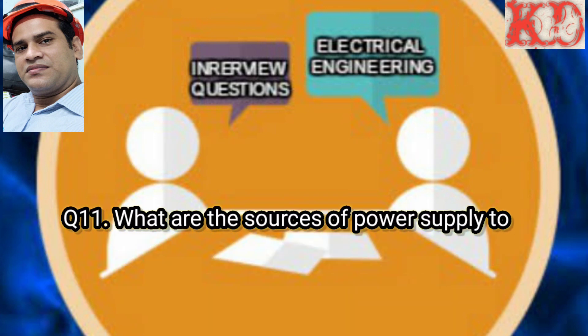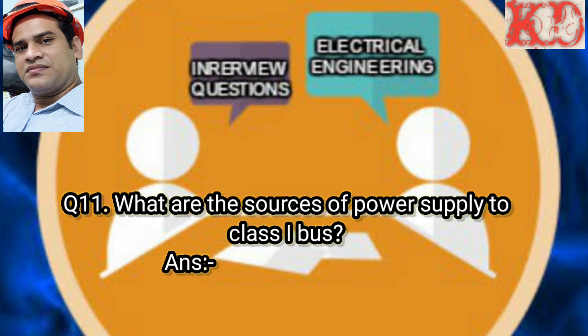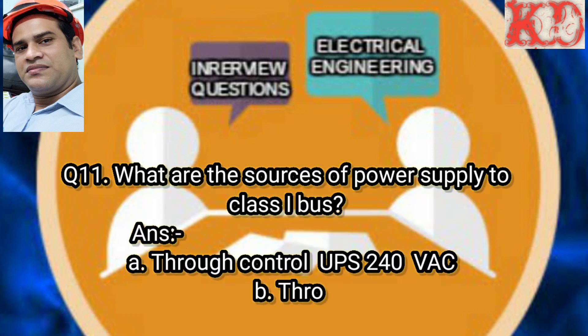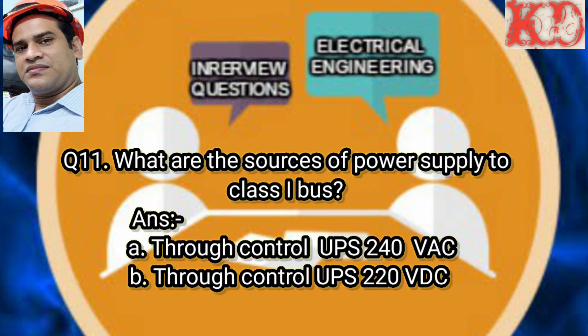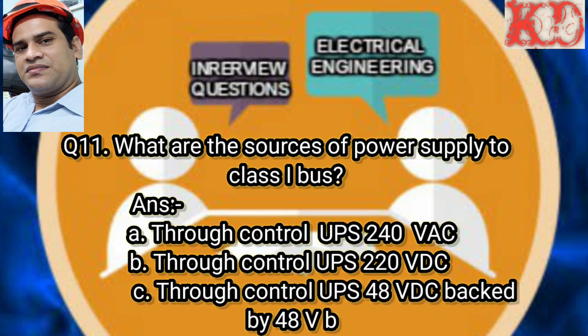Question number 11: What are the sources of power supply to the class 1 bus? Answer: First, through control UPS 240 volt AC; second, through control UPS backed by 220 volt DC batteries; third, through control UPS backed by 48 volt DC batteries.